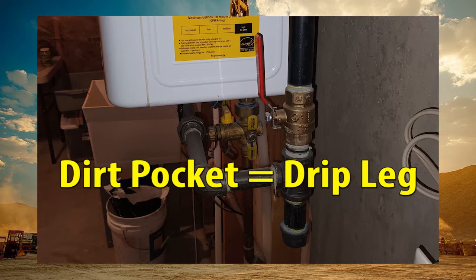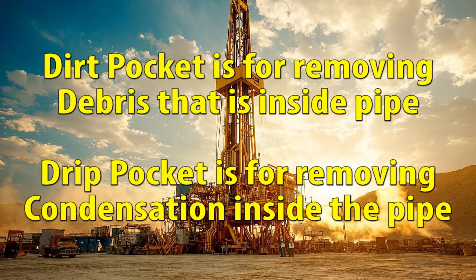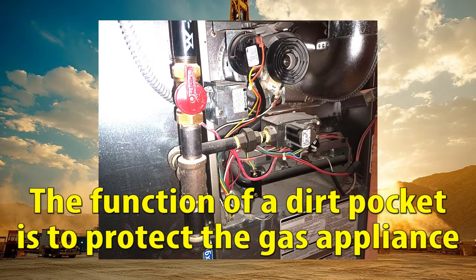The key difference between a dirt pocket and a drip pocket is the drip pocket is intended for condensation. This is an extremely rare occasion where condensation settles out in the gas line. The primary function of a dirt pocket is to protect the gas appliance that is downstream of it.